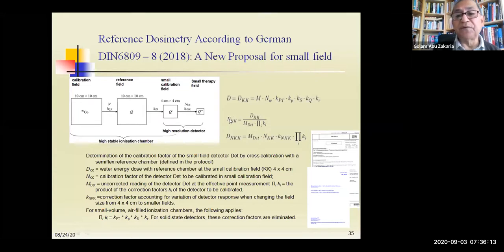When you have the calibration factor, then you have the dose of the small field where you have the readings and the calibration factor, which you determined through the cross calibration, and you put it here. And there is another value, called the correction factor, accounting for variation of detector response when changing the field size from 4 by 4 to a smaller field, just like the correction factor from IAEA. And when you have this, you can correct it. So these are the procedures of the German philosophy.